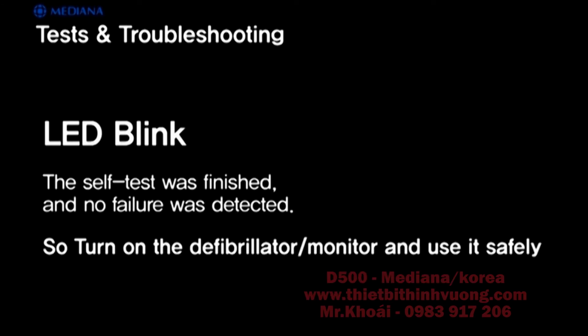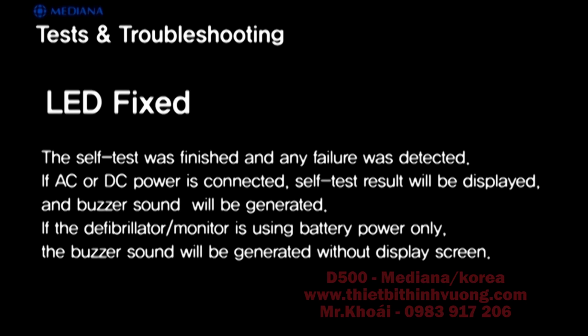LED blinking: the self-test was finished and no failure was detected, so you can turn on the D500 and use it safely. If the LED light is fixed, the self-test was finished and a failure was detected. If AC or DC power is connected, the self-test result will be displayed and a buzzer sound will be generated. If the D500 is using battery power only, the buzzer sound will be generated without the display screen.